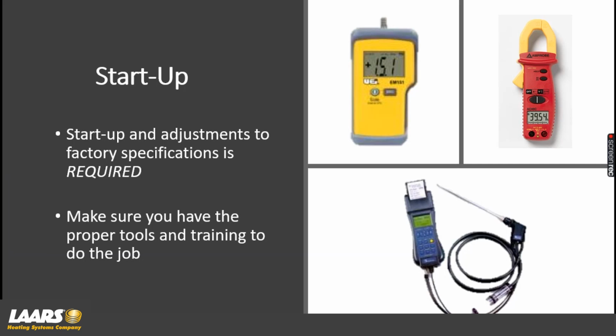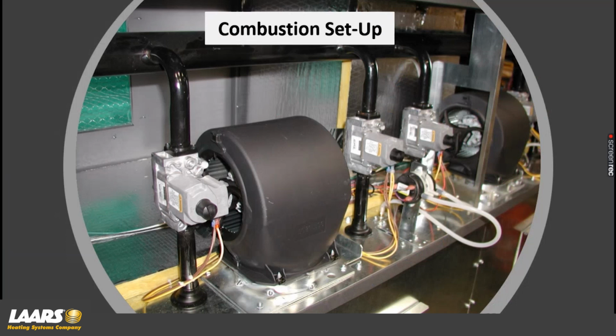With us, we do monitor CO2. So I'm showing here a digital manometer. That's to measure incoming gas pressure and also your manifold pressure. I'm showing an amp probe, so you could measure amperage as well as voltage. And lastly is a combustion analyzer. Over 84% of manufacturers out there tell you that you need a combustion analysis done. For those that don't have one, you really should be investing in it. It's a great revenue source. You can sell customers annual maintenance, come back in and do a flue analysis, and make sure it's running at optimal efficiency, etc. So you need a combustion analyzer.